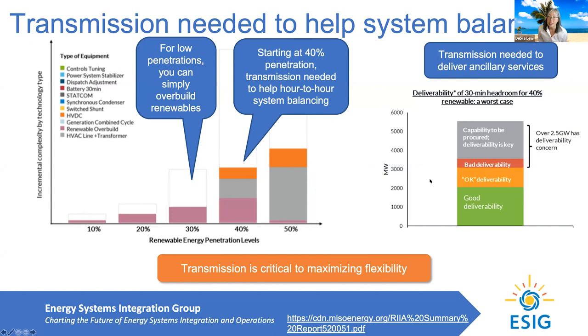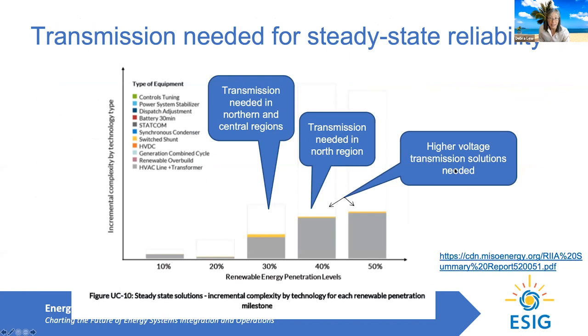One of the things they noted is that transmission is needed to deliver ancillary services. For example, if you've got a lot of solar and you've got a duck curve, you need to make sure that you have 30-minute ramping capability. This shows their worst case situation, how much ramping capability they had, but how much deliverability they had of that ramping capability. Some of that deliverability was questionable, and they needed to build more transmission to deliver that ancillary service.